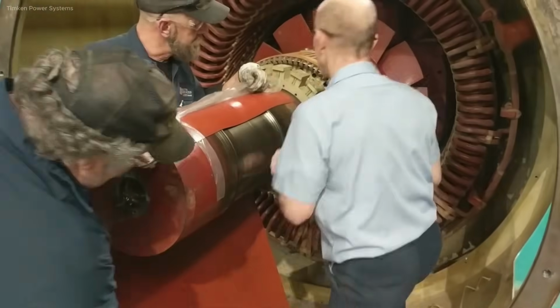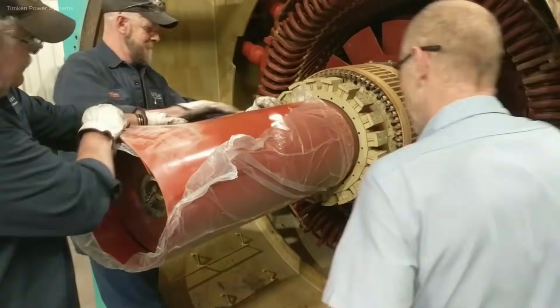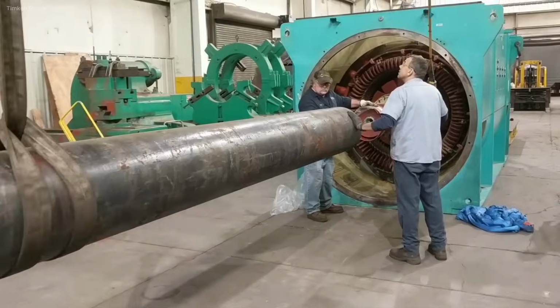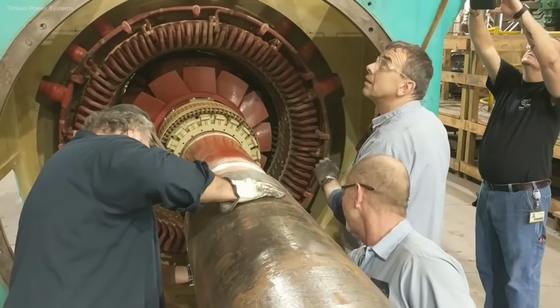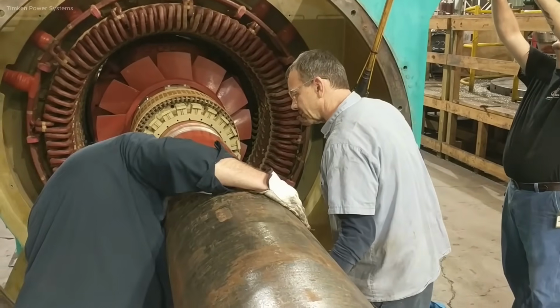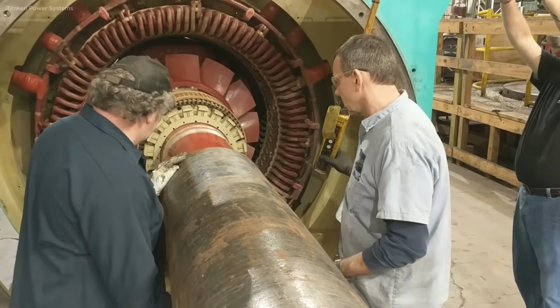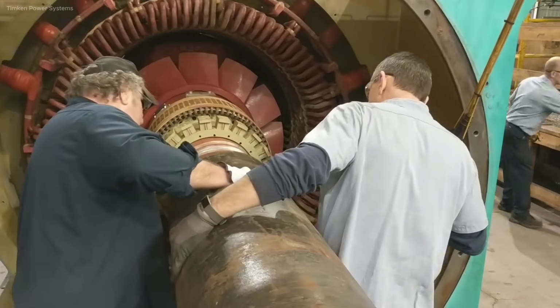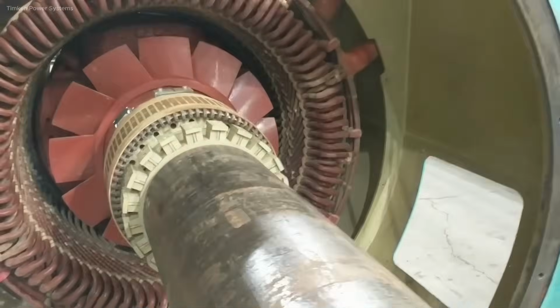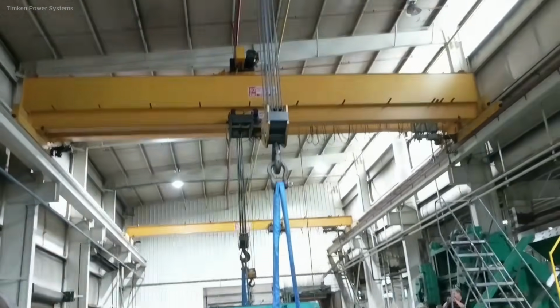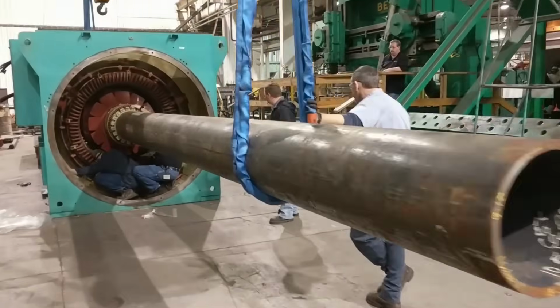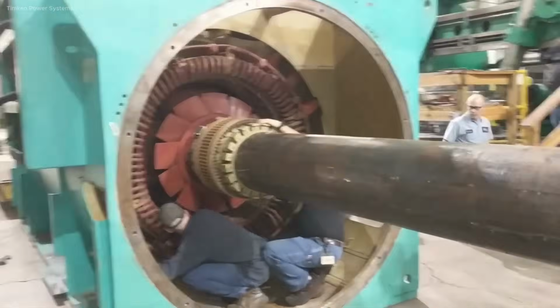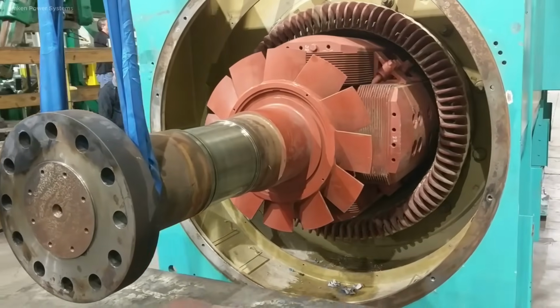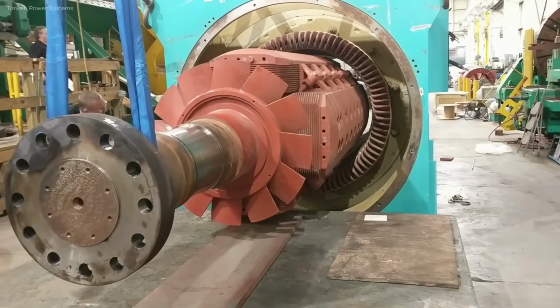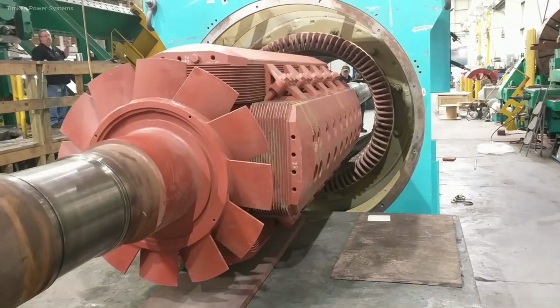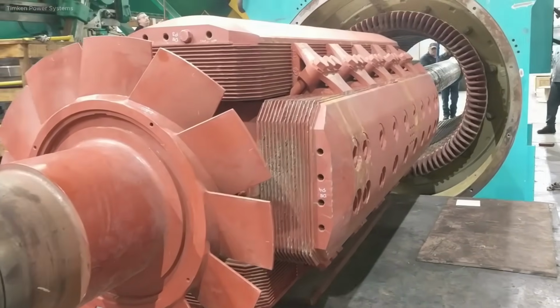The rotor removal process begins by aligning a custom 20-foot steel guide tube with the generator. Two 50-ton cranes carefully lift and support the 45,000 lb rotor. Using the guide tube and a hydraulic system, the rotor is slowly floated out of the 32 megawatts generator stator, maintaining a clearance of only 3/4 inch. Enerpac's hydraulically actuated system ensures precise control and reduces manual labor and time during removal.